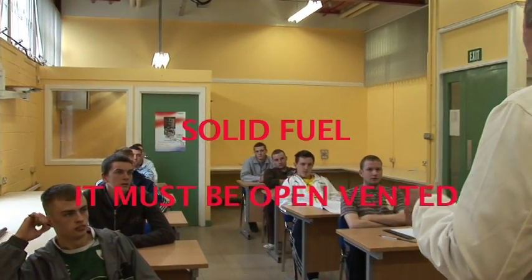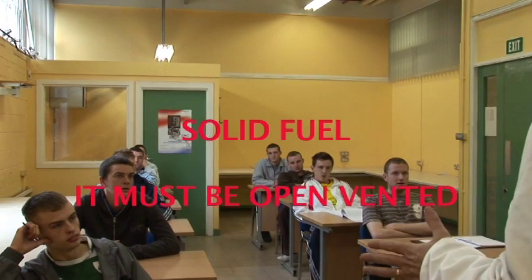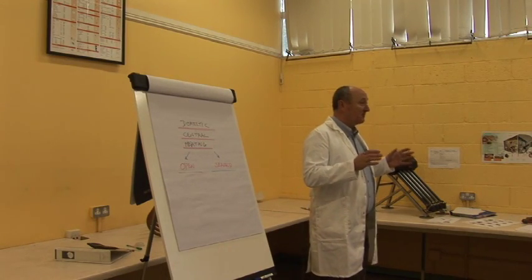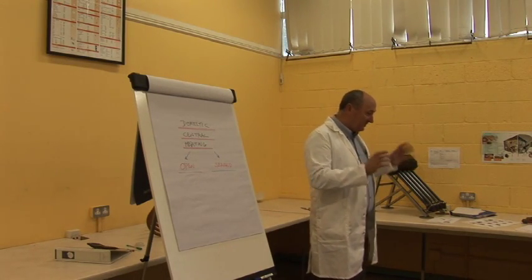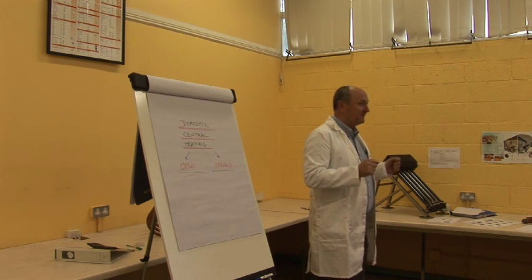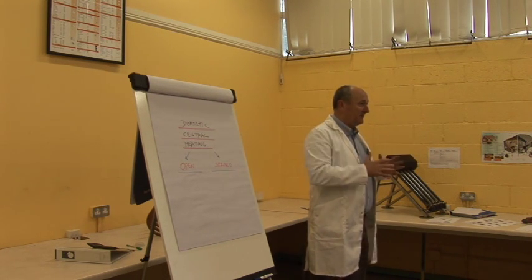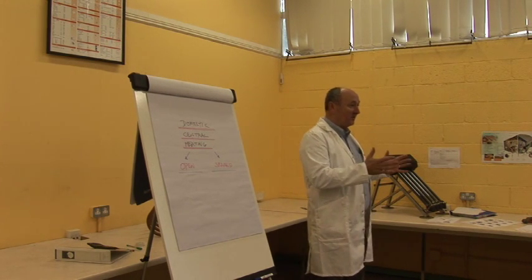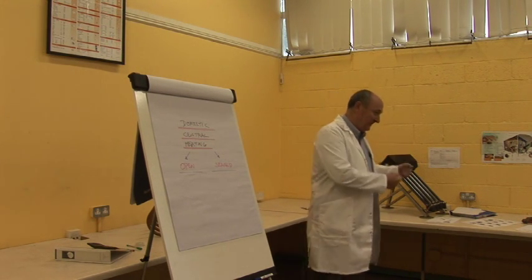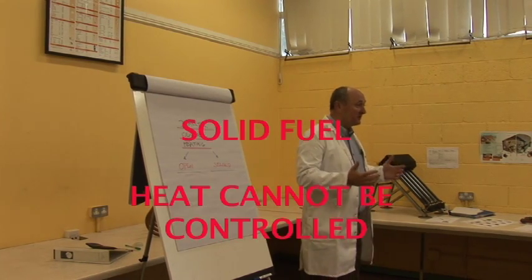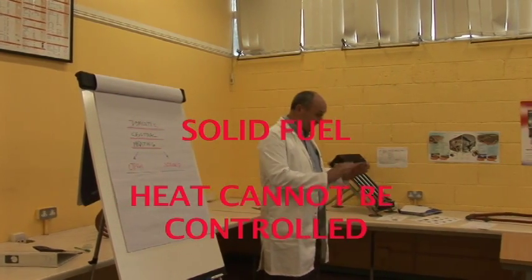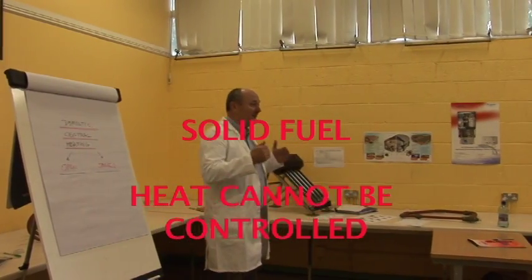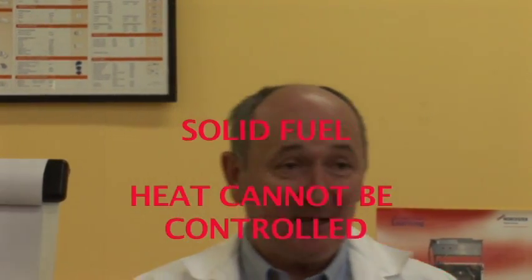On the open vented system, you must have a gravity circulation. What gravity means is that when somebody lights the fire, the heat has to be able to get away safely — nothing aiding it. You can't depend on a pump or electrics, because with solid fuel if somebody keeps putting on material it will just keep taking it. So you have to build in a gravity circuit.